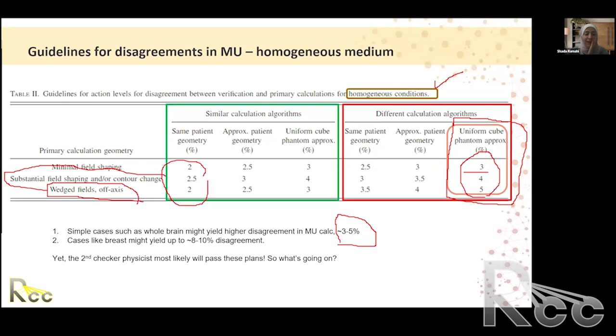Now, if we're talking about heterogeneity correction, where you are doing the plan in the TPS using heterogeneity correction, which I recommend, so don't turn off heterogeneity corrections in your TPS, then if I'm using the same patient geometry, I should expect up to 5%. But in manual MU calculation, I can only use the assumption of a cube phantom. So how much should I expect? That's a big question. That is missing from the report. And people need to ask, why is that missing from the report?